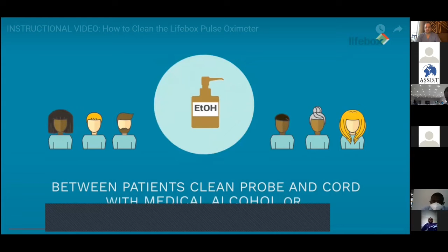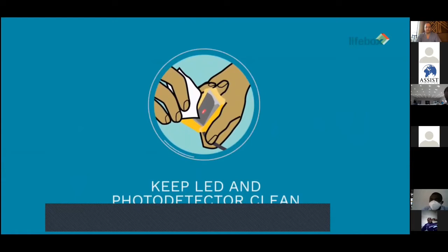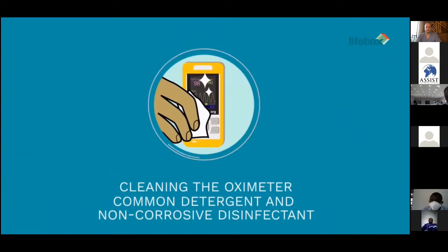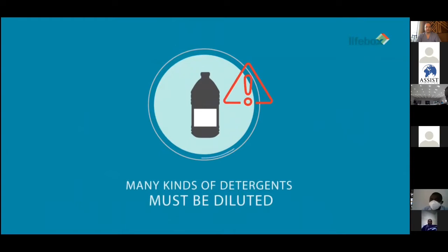Between patients, it is essential that you gently clean the probe and cable with medical alcohol. Small amounts of 70% alcohol-based hand rub will also work, but should be applied sparingly. It's important to keep the LED and photo detector clean. Please also remember to wash your hands, following proper protocol between patients. The oximeter should be wiped down regularly, using common detergent and non-corrosive disinfectant, such as those used in hospitals. Be aware that many kinds of detergents must be diluted prior to use.